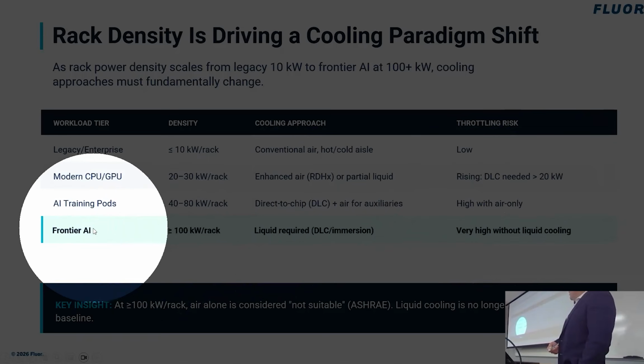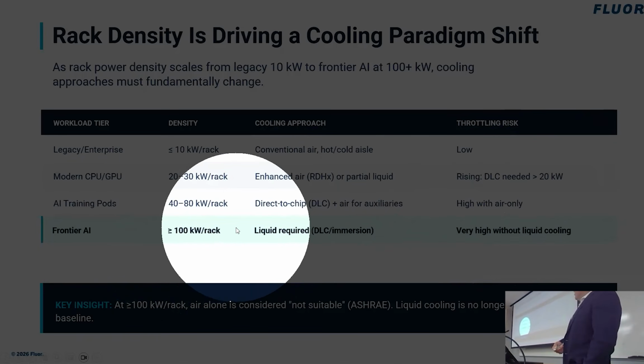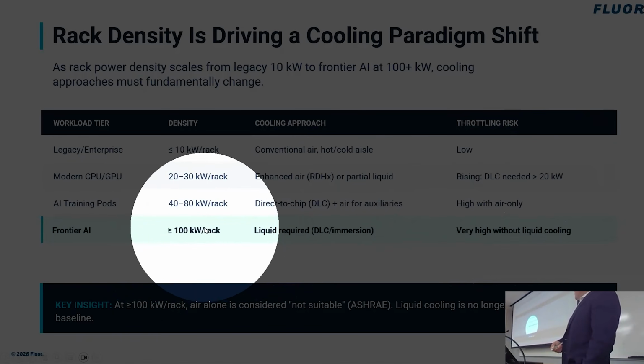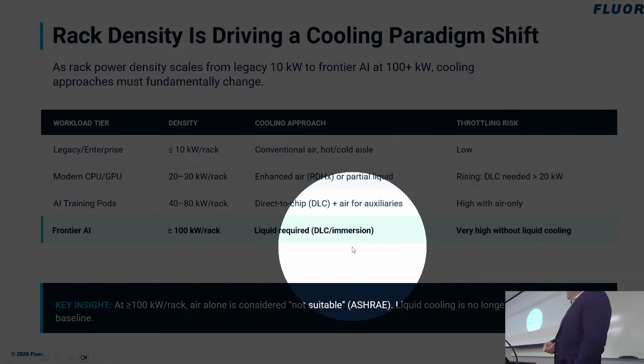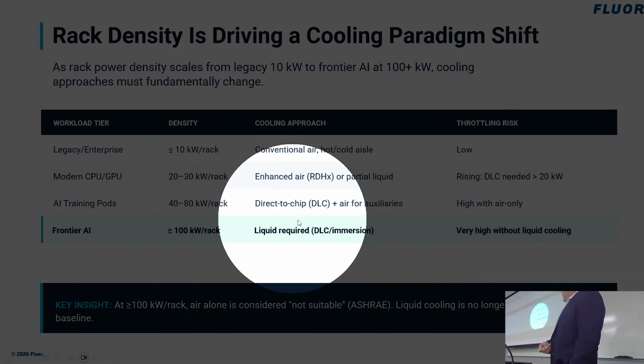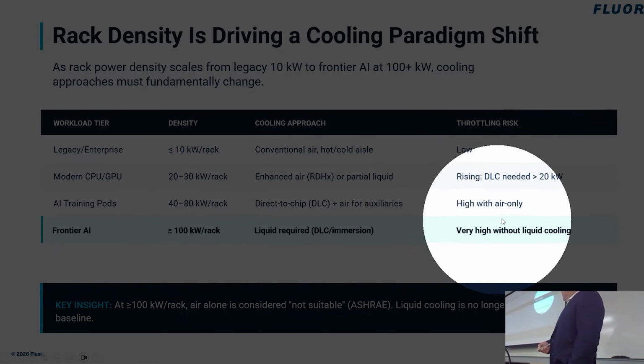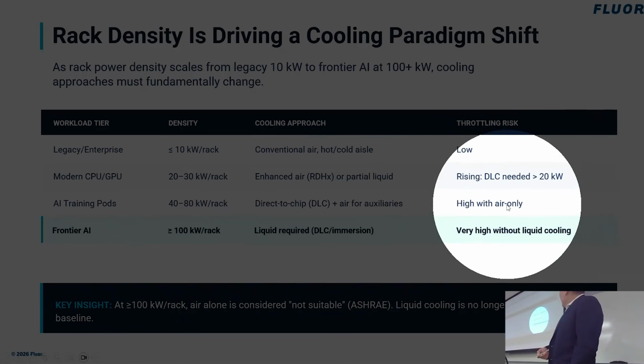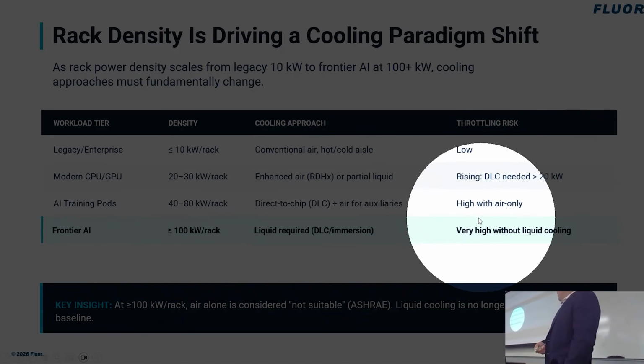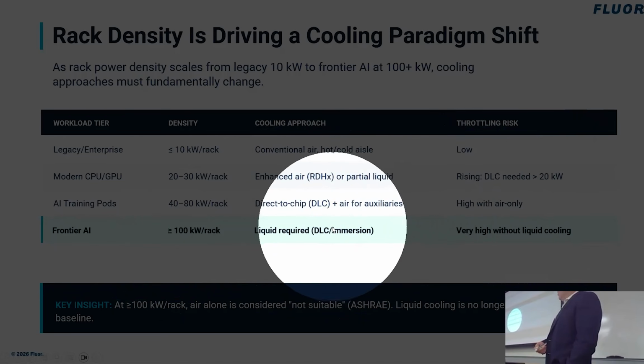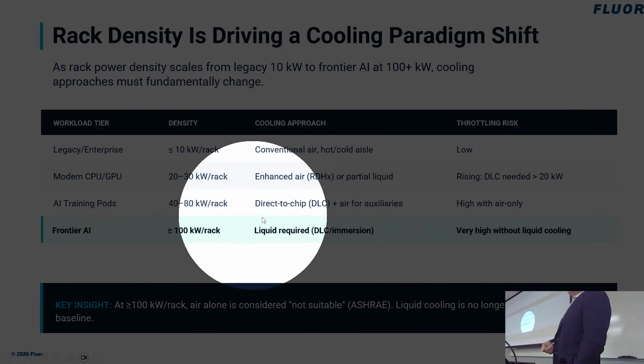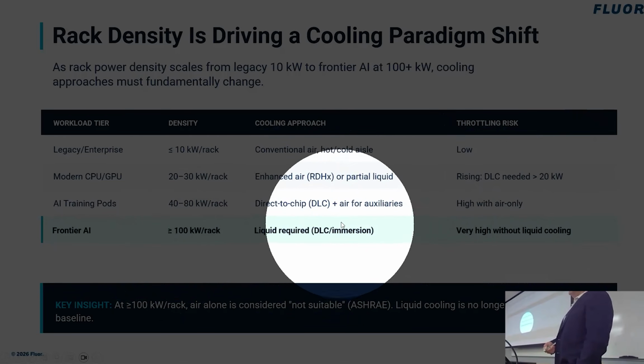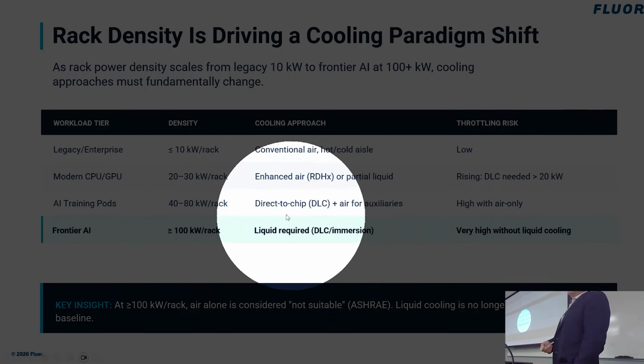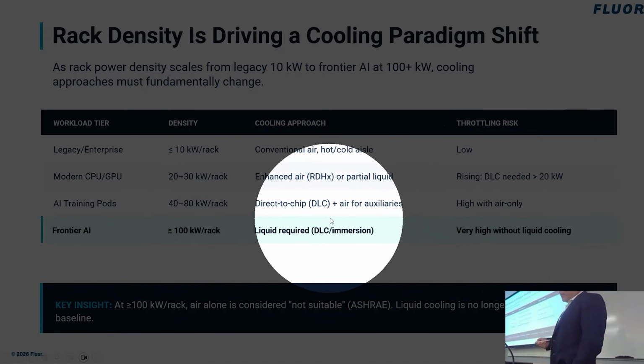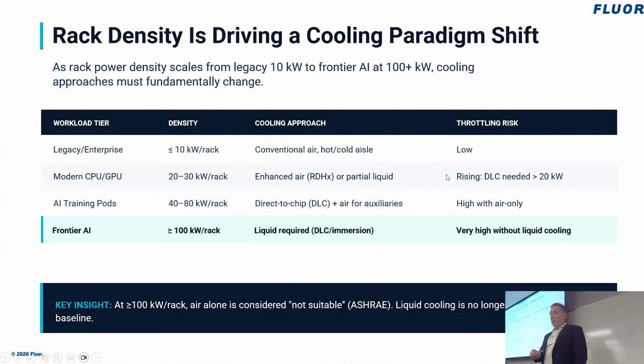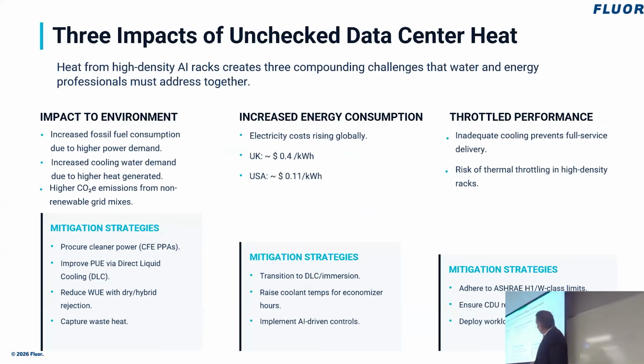Finally, where we are right now, is with generations of more than 100 kilowatts per rack. In these cases, to lower the risk of throttling the units, the heat has to be recovered using a combination of liquid system plus air system, because air alone is not enough.